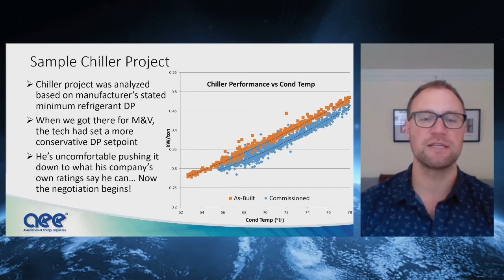So now is where the negotiation begins. I think on this project in the end we met somewhere in the middle, maybe 2 or 3 PSI, but the point is we were able to squeeze an additional 10% or so of energy savings, which is the difference between the orange and the blue trend lines here on the chart, for a minimal amount of effort. Sometimes it takes several rounds of iteration and a lot of back and forth negotiation to get this stuff right. It probably took us 6 weeks to finish this M&V, where otherwise it would have taken 2. But in terms of man hours, it was practically nothing. It's just a set point, right? So it's well worth the effort to dig a little deeper.